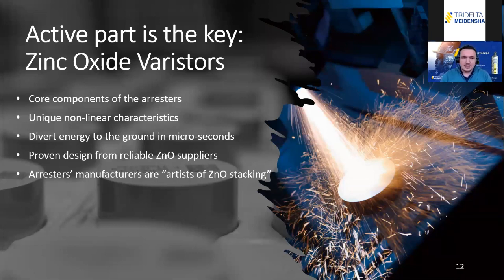So now we'll talk about the zinc oxide varistors or metal oxide varistors. Everybody knows that this is the core component of the arresters. They have a very special, unique characteristic, which is a non-linear function. I will go into the details, but basically they behave as an insulator under nominal voltage, and they are able to conduct extremely fast the transient of a voltage in a safe way. So in that case they divert the energy to the ground in microseconds.